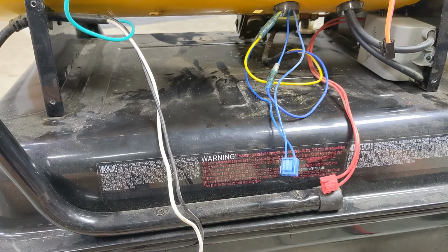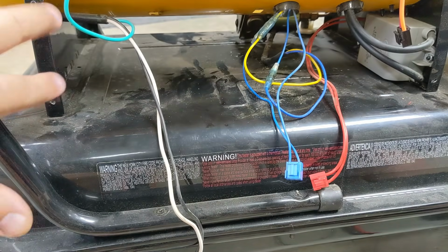I think from listening to this thing fire up before, the order of things was the fan kicked on, then the igniter, then the fuel. It may be that the fan kicked on, then the igniter, then the fuel pump, then the solenoid. I'm not really sure. I'm also not really sure that it matters. Seems to me that the fuel and the fuel solenoid opening would come on at the same time, because that way when it starts pumping, it has a place to go. It's not blocked by the solenoid cutting off the flow. So not sure, but there is a panel that goes across this surface.